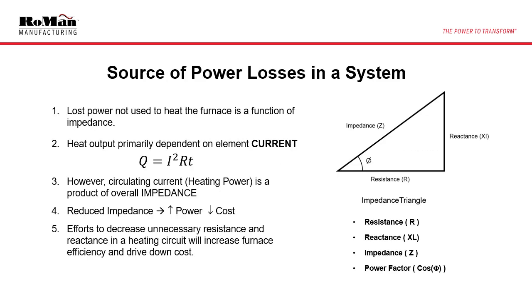The source of power losses in an AC electrical system can be attributed to overall impedance. Similar to the power triangle, the impedance triangle here shows resistance and reactance 90 degrees out of phase. Resistance generates usable power output, whereas reactance generates lost power output. In a system with a fixed resistance, heat output is primarily dependent upon current, as shown here with Joule's law. In an ideal system, we want the only resistance in the circuit to generate heat in the furnace. Any unnecessary resistance or reactance creates power losses. When we reduce impedance, we get more power for less cost. Let's examine how we can do this.